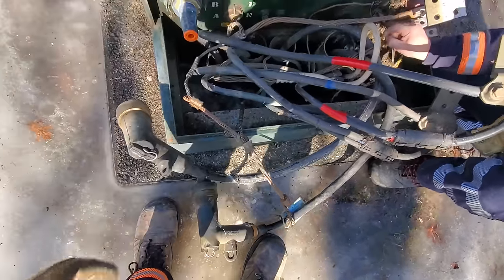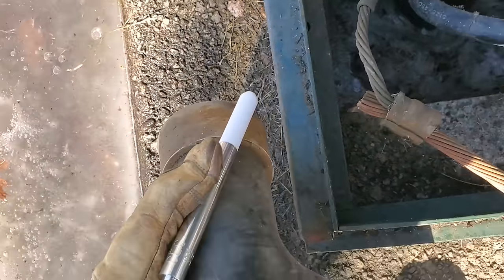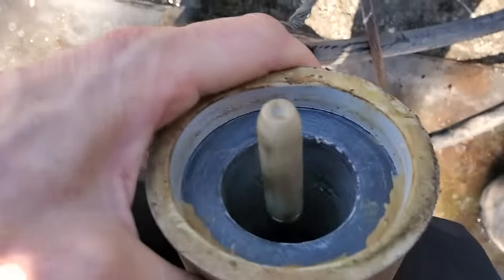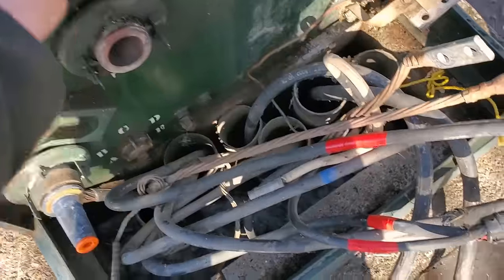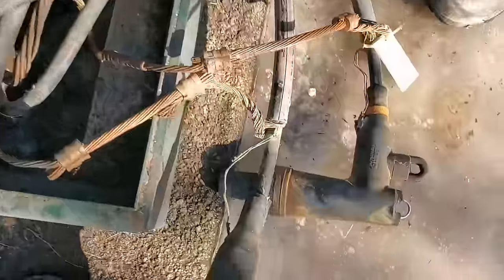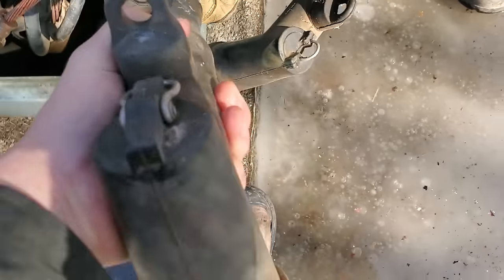That stinger, that's the connection that connects from the high voltage termination in through the insert. That white tip on there, that's a load break tip. This device I'm using here is pretty much the most primitive way of installing those at proper torque. Basically that little wire that I just showed you, when you tighten that stinger, it'll bend once it's at proper torque. But while we're waiting for material, we don't have anything on site at all yet, so we're just kind of stripping things apart, taking a little bit better look.